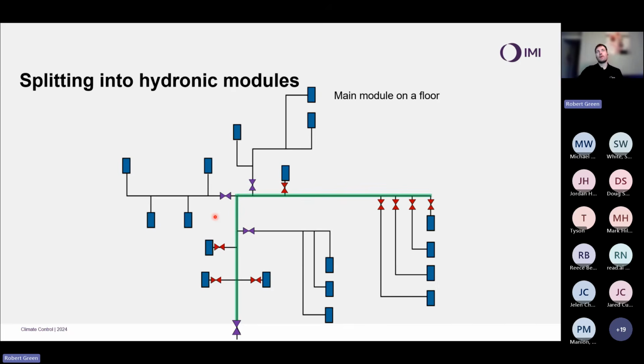One key thing to notice, and I want to point this out at this point here, we don't need a manual balancing valve left and right. We just follow the path of the main flow in order to optimize both capex, how many valves we need to buy, and opex, minimizing my pumping costs. We do not want to end up putting valves in series with each other. So therefore, we do not require a valve here.